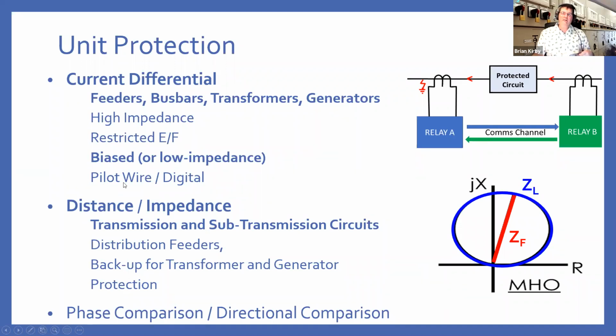I've mentioned communications. Pilot wire is analog. If you think of something like a 4 to 20 milliamp current loop, it's that sort of thing. You would send a current from one end to the other. But again, that's very rarely used today. Today, it's largely digital communications because that is the norm for most things. So this channel today will typically be your relay plugged into a multiplexer onto a gigabit backhaul, and it will be transmitted across your network on a fixed link path to give you deterministic comms delays. I won't go into the details, but that is important for your protection. You need to know how long the communication is going to take.